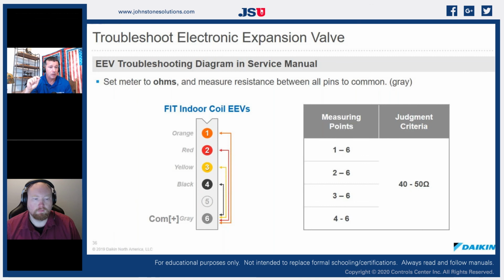We're going to put our meter on ohms, and we're going to check between number 6, which is the common point, and check 6 to 4, 6 to 3, 6 to 2, 6 to 1. All of those should be between 40 and 50 ohms. If it's outside of that range, it's bad. It's that simple. It means that it won't allow it to open and close properly.